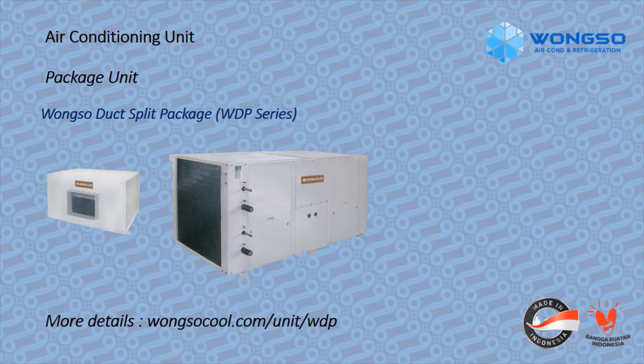Package unit yang lainnya adalah Wongso Ducted Split Package atau WDP series. WDP series ini terdiri dari indoor unit, yaitu WDS atau Wongso Split Duct, dan juga outdoor unit WCU atau Wongso Condensing Unit. WDP series ini memiliki range dari 3 sampai 40 HP dengan variasi 1 dan 2 sirkuit dengan cooling capacity mulai dari 30.000 hingga 400.000 BTU per hour.